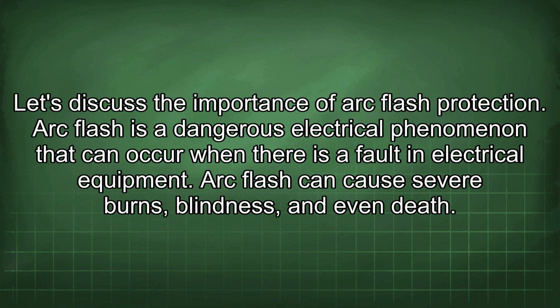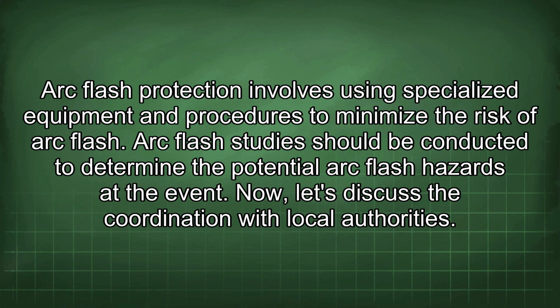Let's discuss the importance of arc flash protection. Arc flash is a dangerous electrical phenomenon that can occur when there is a fault in electrical equipment. Arc flash can cause severe burns, blindness, and even death. Arc flash protection involves using specialized equipment and procedures to minimize the risk of arc flash. Arc flash studies should be conducted to determine the potential arc flash hazards at the event.